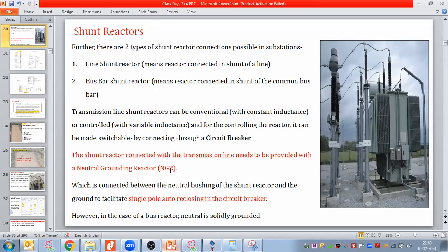Another piece of equipment would be required in the substations. Why it is required, I will tell on this. I will come on this. So the shunt reactor connected with the transmission line needs to be provided with a neutral grounding reactor, NGR, which is connected between the neutral bushing of the shunt reactor and the ground. Why? To facilitate the single pole auto reclosing in the circuit breaker.